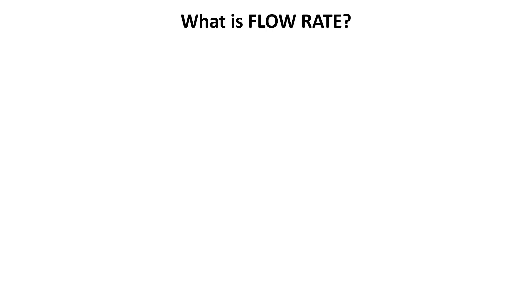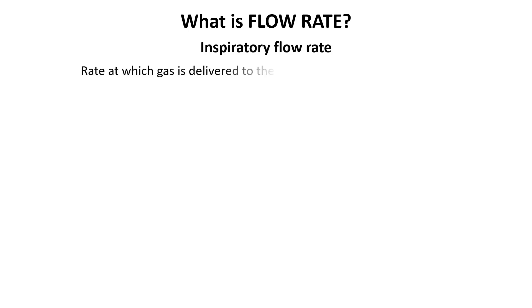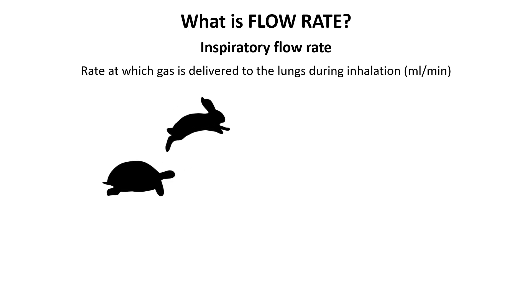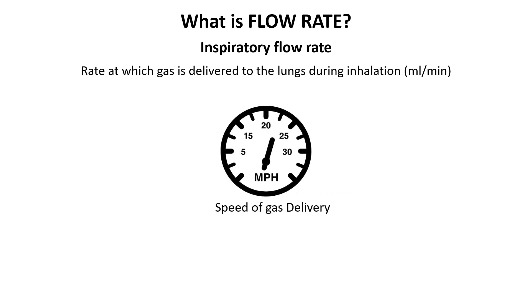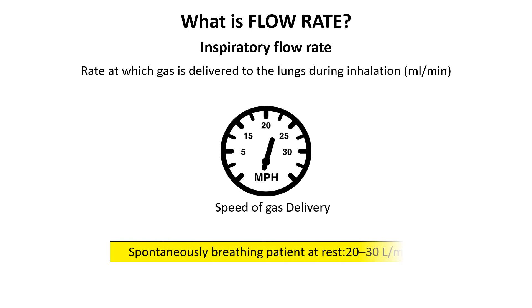A ventilator's flow rate, or inspiratory flow rate, is the rate at which gas is delivered to the lungs during inhalation. It gives us a measure of how quickly or slowly gas like oxygen is delivered to a patient's lungs. For a normal spontaneously breathing patient at rest, the typical inspiratory flow rate is around 20 to 30 liters per minute.